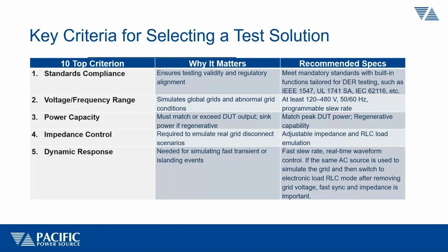In order to accomplish this, there's a number of things that the test equipment has to be able to do. First of all, it has to meet the grid simulation requirements in terms of voltage, frequency, accuracy, and stability, in order to meet the requirements for the IEEE, UL and IEC standards. It has to be programmable, obviously, to simulate different grid voltage and frequency combinations, so you have the ability to test for any region or country. That also means you need to support 120 or 240 volts, or three-phase 400, 380 or 480 volts. Typically 50 or 60 hertz is most common for DERs because they're grid connected, and you have to be able to program all those functions accurately.